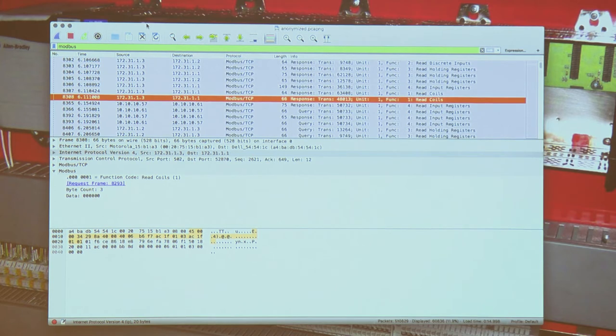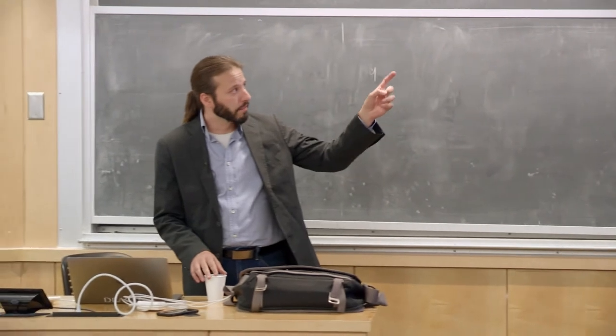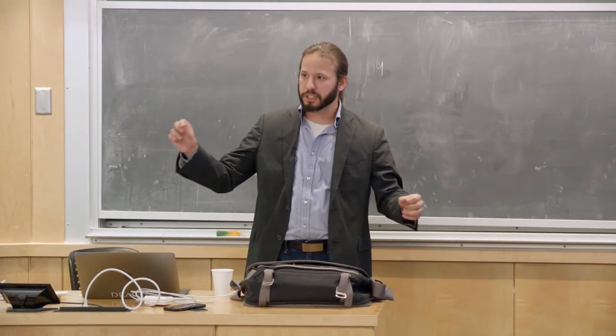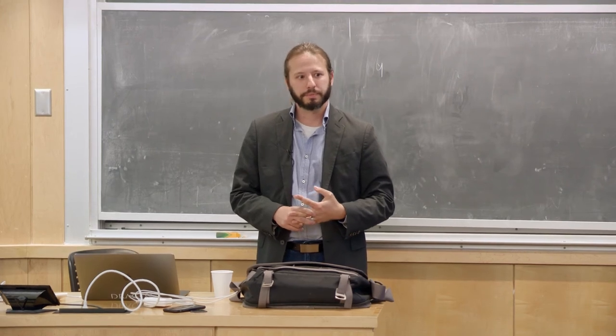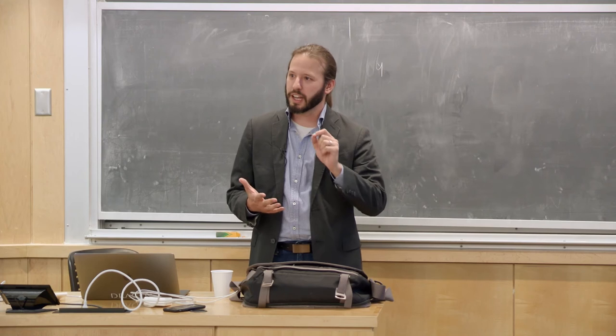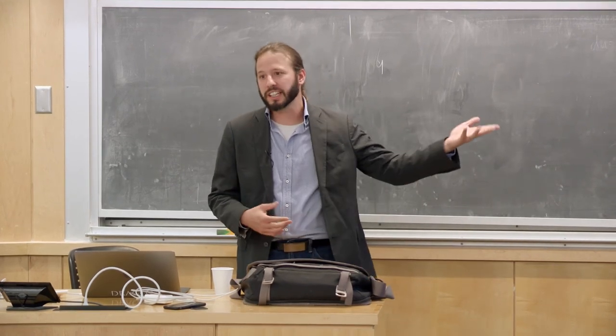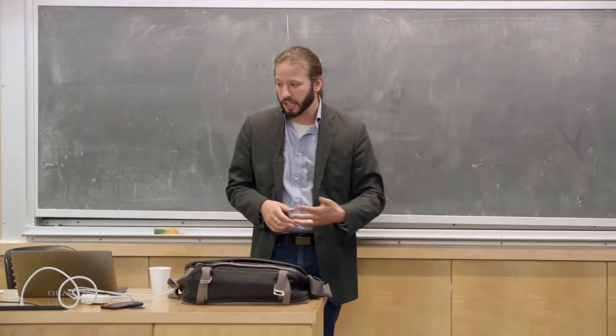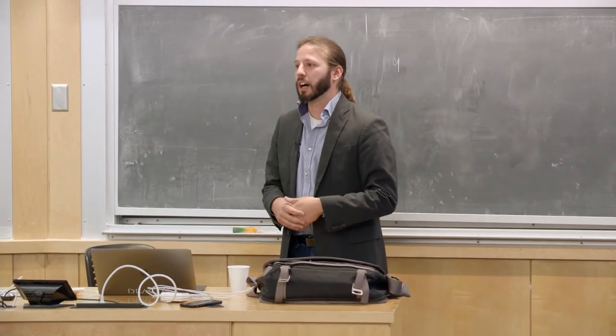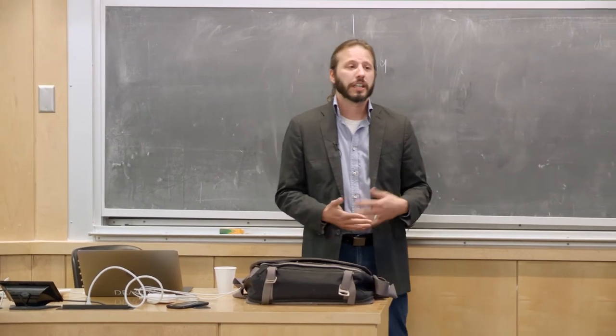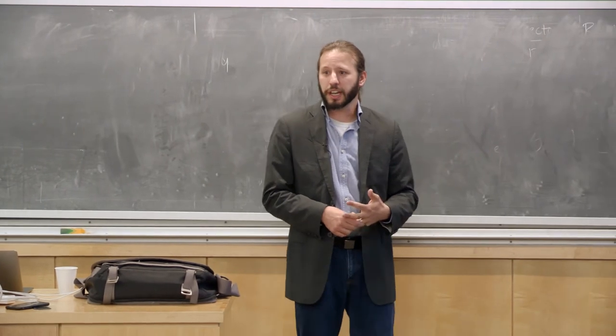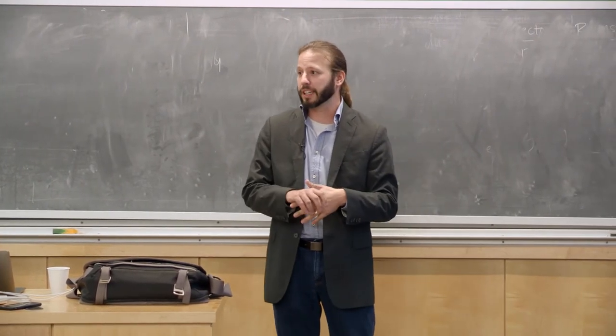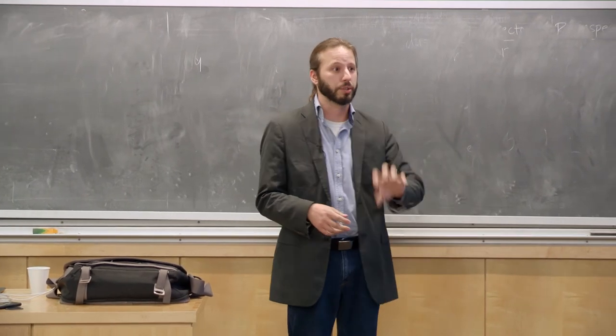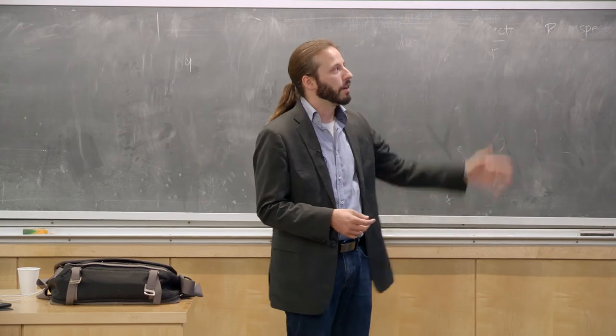So I mentioned Modbus earlier. Modbus is a serial link that has history in serial links similar to that from the PLC out to the field devices, where it's basically talking down one wire in a binary fashion, in a very repeatable fashion, and that's called Modbus, the actual architecture there. That's been mapped over to TCP/IP. When they were trying to figure out how to get more interoperability and communications, they had this thing called Ethernet and this thing called TCP/IP back in the 90s, and they said, all right, well, we'll just encapsulate the serial protocol over TCP/IP. And thus you have Modbus TCP/IP.